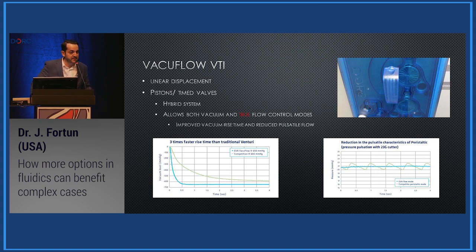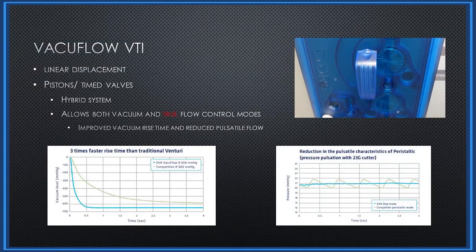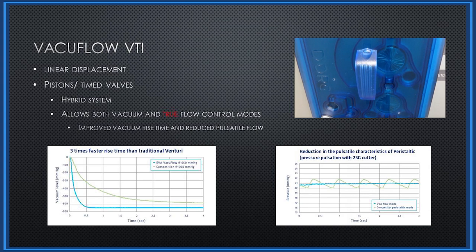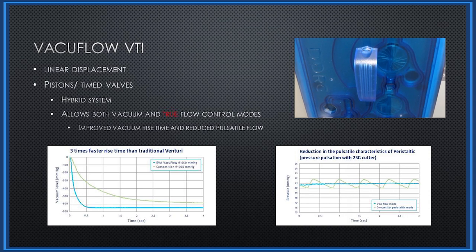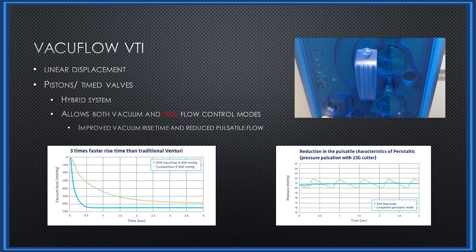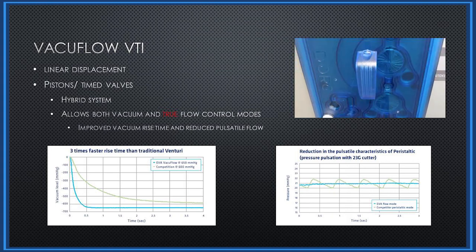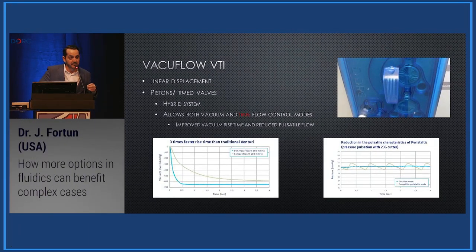What's innovative about the DORC EVA is a system called VacuFlow VTI, which provides the best of both worlds for peristaltic and Venturi pump systems. It's technically called a linear displacement system consisting of pistons and timed valves — a hybrid system. It gives you a faster rise time than a traditional Venturi pump while also delivering less pulsatile flow than a peristaltic system. Not only does it combine the best of both, it improves on both in significant ways.